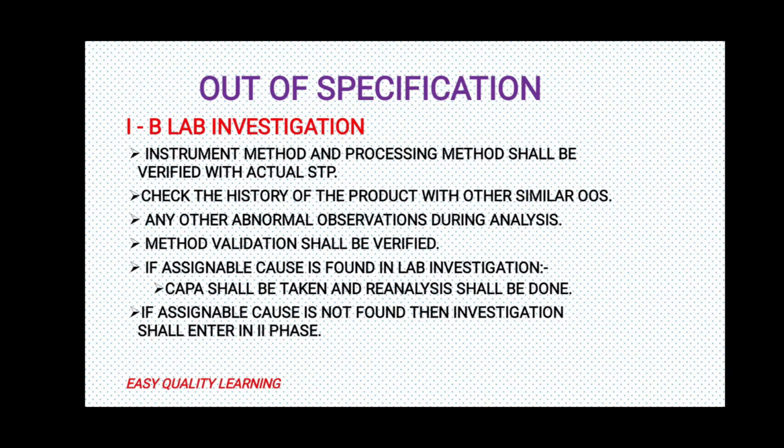If the assignable cause is found in lab investigation, then CAPA shall be taken and reanalysis shall be done. If we found that some lab error was there, we need to correct that lab error, and CAPA regarding that lab error should be taken, and we need to do the reanalysis of that same sample. And after reanalysis, if the results are complying, we need to report passing results as well as OOS results, and a decision shall be taken accordingly.